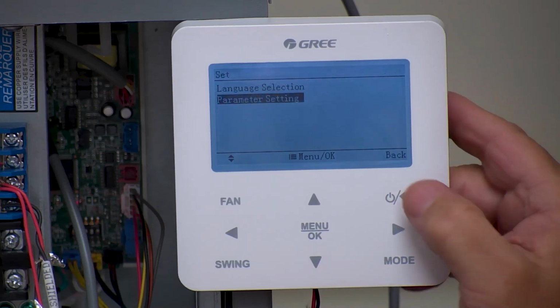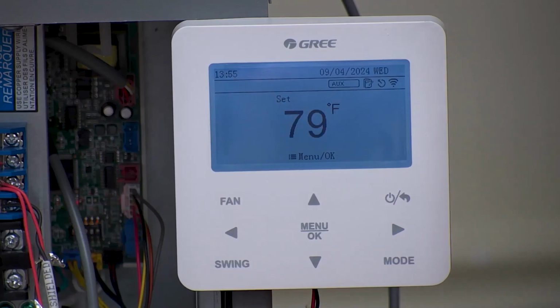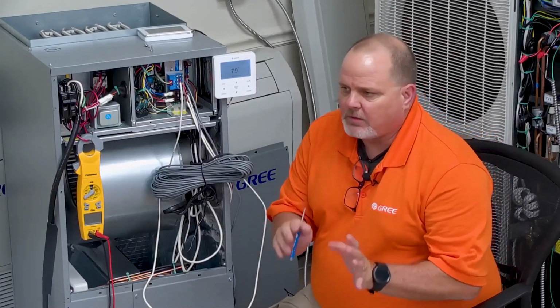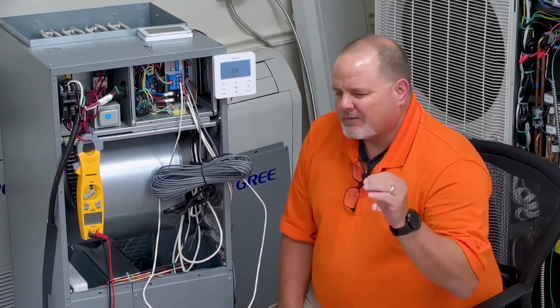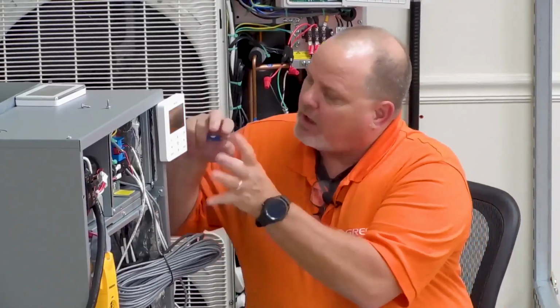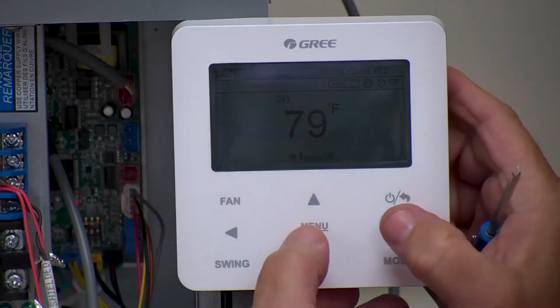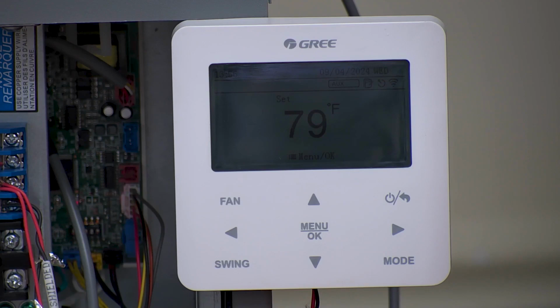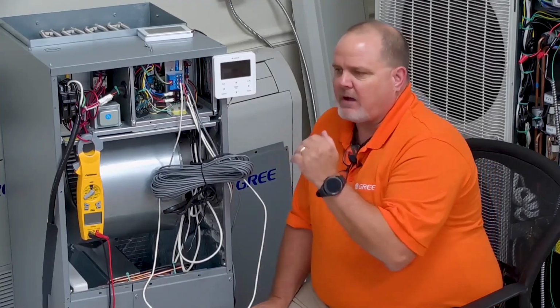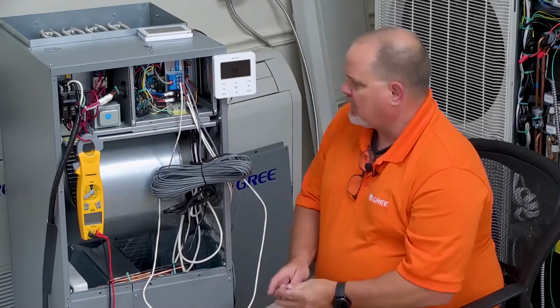And then we can go back to the main screen. Now, the controller doesn't come set up for eHeat function, and they should have it set up for you, or I'm sorry, not set up for you, but in the installation instructions. So if you have electric heat available, again, only on an air handler, when you first power it up, before you even turn it on, you hold the menu and power for at least 5 seconds, and it'll say setting is done. That means you now have the eHeat function, or eHeat mode, I should say. It doesn't come out of the box with eHeat mode. You have to enable eHeat mode.